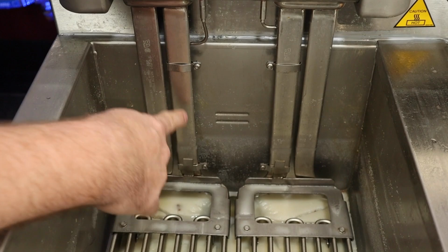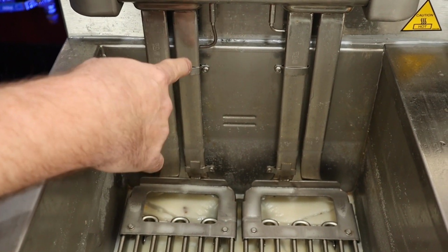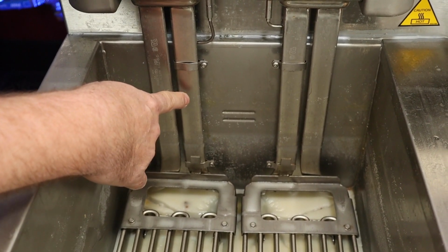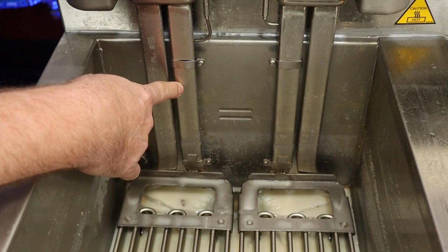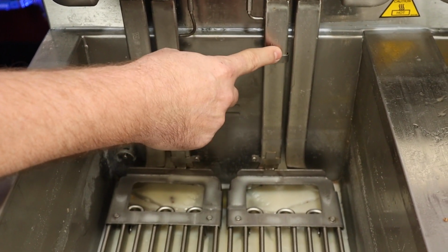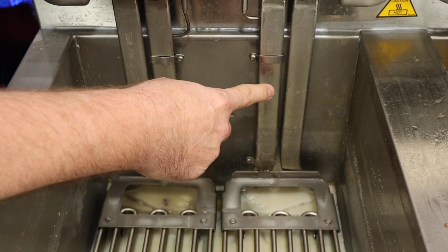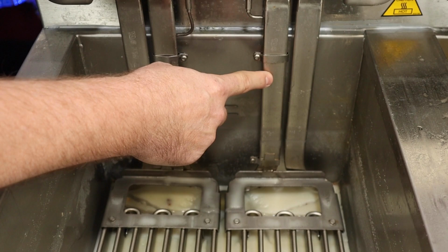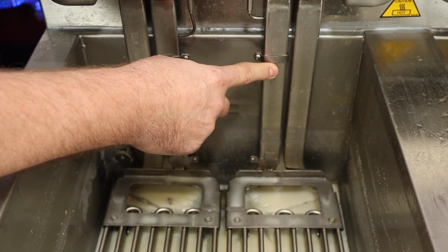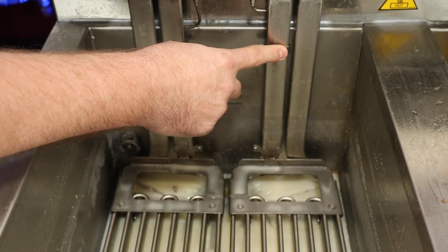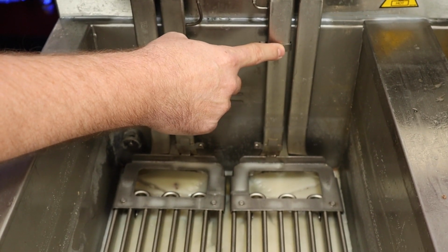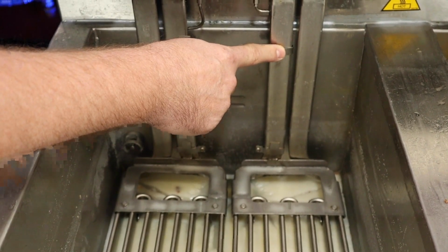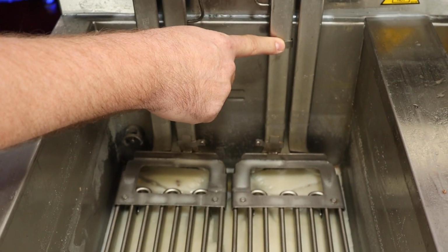So that high limit PCB will check the temperature on this, and then it will check it again, and if it's greater than 63 degrees Fahrenheit or 35 degrees Celsius, that's when the E10T error code will occur. It will do the same thing over here and check this probe twice as well. And again, if it receives feedback greater than the temperature difference that we mentioned, that's when the E10T will occur. So for a split VAT, since we would only have 1 high limit probe, it's going to check that same probe twice, and again, if we see that temperature difference of greater than 63 degrees Fahrenheit, 35 degrees Celsius, that's when the error code will occur.